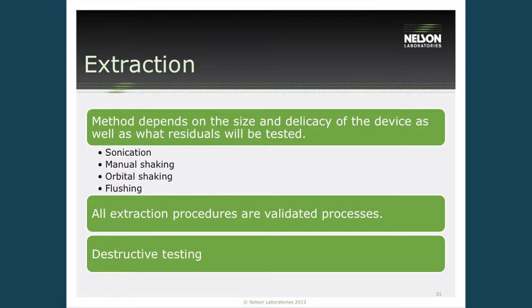Next, you extract the devices to ensure that we're removing anything off of the devices, whether it's the positive control device or all the clean devices, to make sure everything was fully removed in the cleaning process. This can occur a number of ways depending on the device type and also the residuals that we're looking for. It can be performed by sonication, manual shaking, orbital flushing.